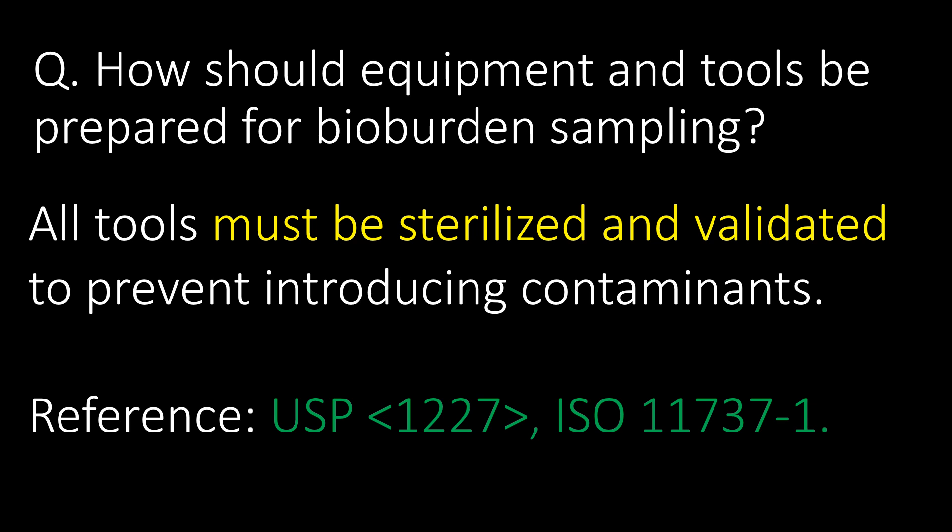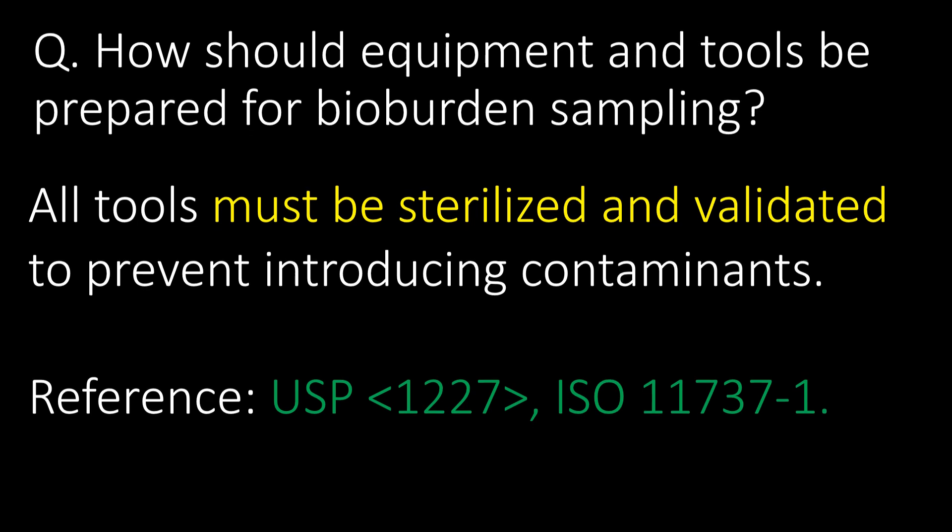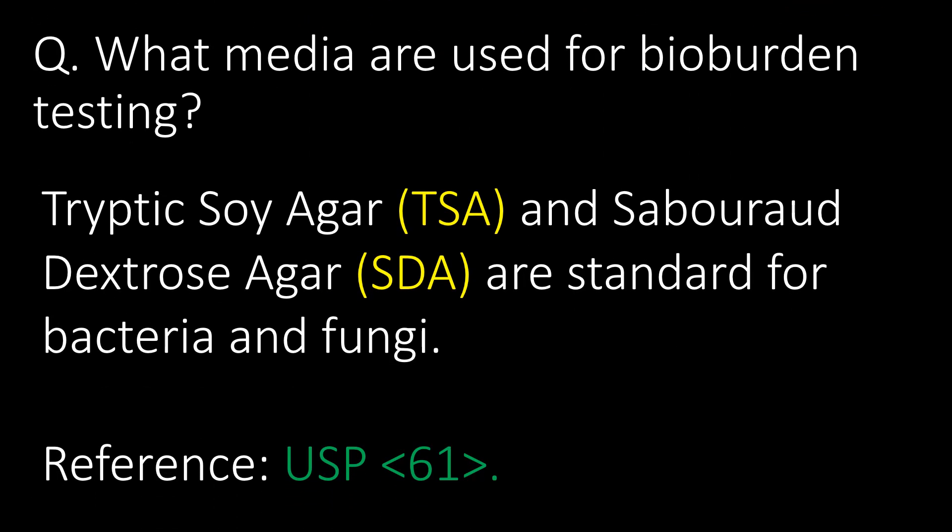How should equipment and tools be prepared for bioburden sampling? All tools must be sterilized and validated to prevent introducing contaminants. Reference USP Chapter 1227 and ISO 11737-1. What media are used for bioburden testing? Tryptic soy agar (TSA) and Sabouraud dextrose agar (SDA) are standard for bacteria and fungi. Reference USP Chapter 61.